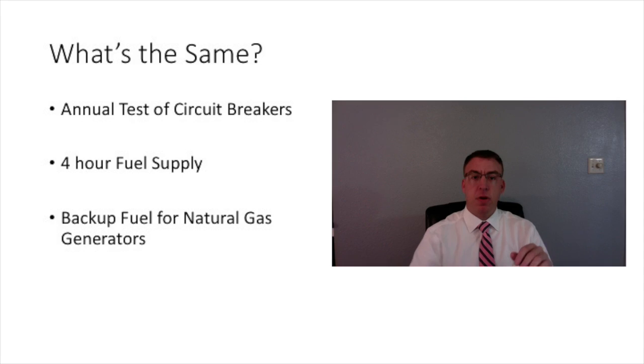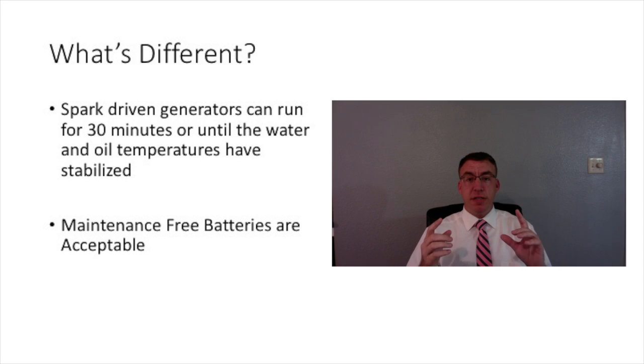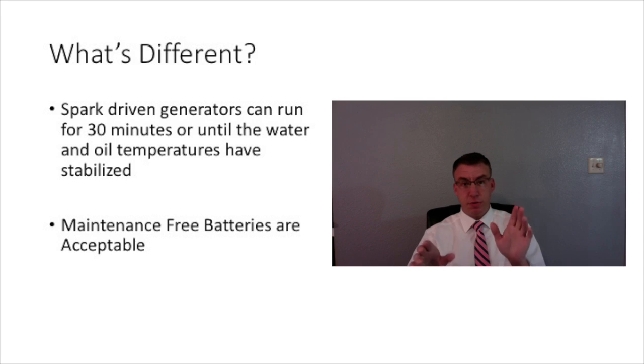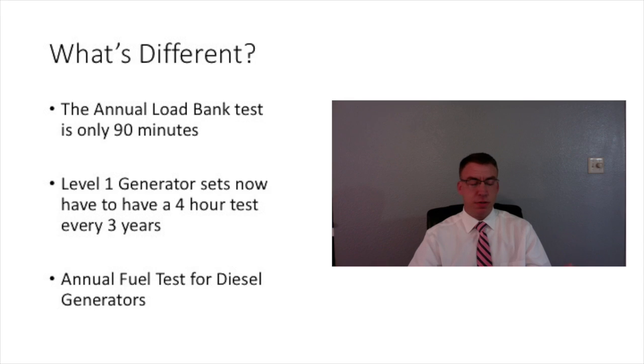Now, so what's different? The test of the spark-driven generators, such as propane, natural gas, and gasoline, which I would never recommend because gasoline sucks nowadays, those can actually be 30 minutes or until the water temperature or the oil temperature has equalized, whichever's later. It's probably going to be the water temperature at 210 after so long. You can now have maintenance-free batteries. You have to do a quarterly conductivity test, basically a load test on the battery.